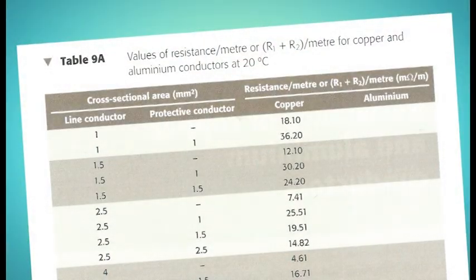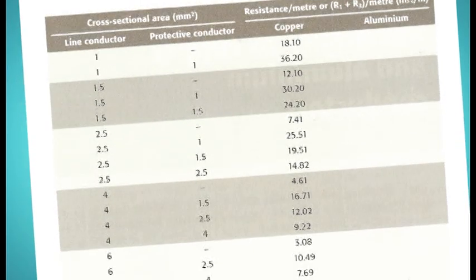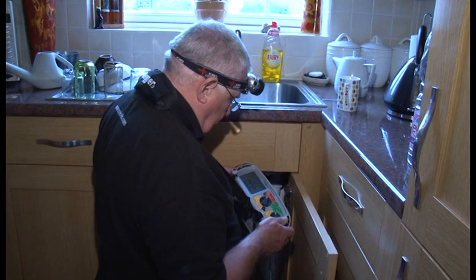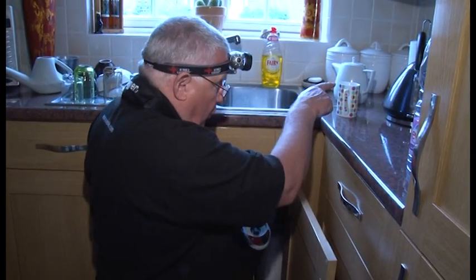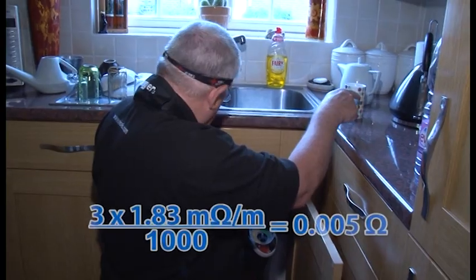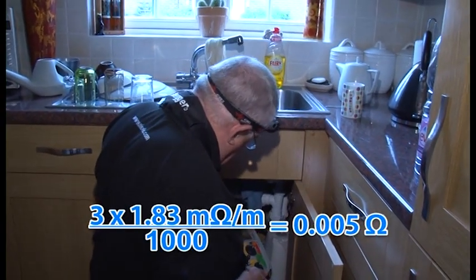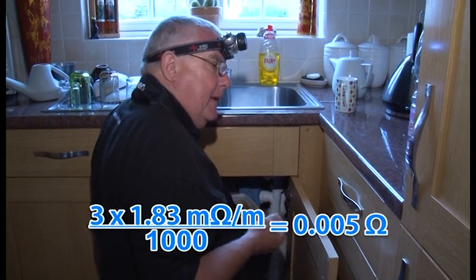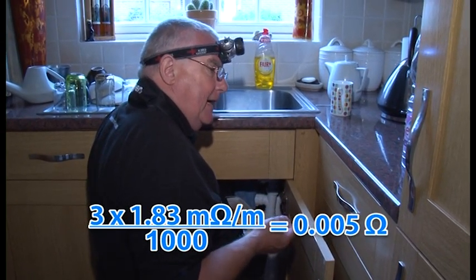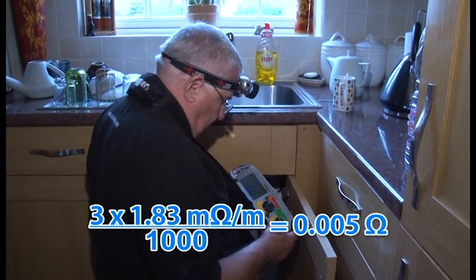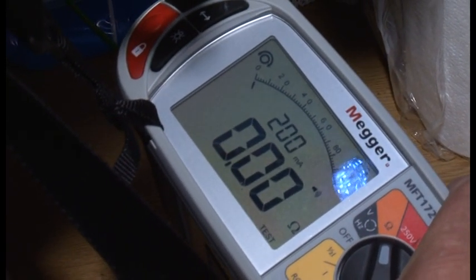When measuring the resistance of a conductor, you can use tables in the on-site guide to calculate a comparison value. For example, a 10mm squared copper conductor has a resistance of 1.83 milliohms per metre. Well, is this reading of 0 realistic? Well, if that wall wasn't there, I could more likely touch the consumer unit. So the length of the cable is only about 2 to 3 metres. Now, if you consider the resistance of 10mm cable of 1.83 milliohms per metre, it's very, very small. And I would imagine the resolution of this instrument can't measure that low. So 0 would have to be okay for this. I will now go and repeat this for the gas, and the procedure will be exactly the same.